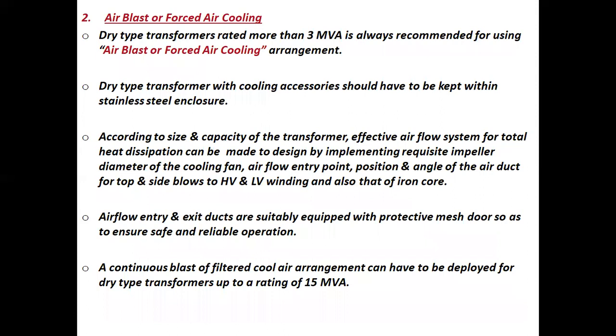Number two, air blast or forced air cooling. Dry type transformer rated more than 3 MVA is always recommended to use air blast or forced air cooling arrangement. Dry type transformer with cooling accessories should be kept within a stainless steel enclosure. According to size and capacity of the transformer, an effective airflow system for total heat dissipation can be designed by implementing requisite impeller diameter of the cooling fan, airflow entry point, position and angle of the air duct for top and side blows to the HV or LV winding, and also that of the iron core.